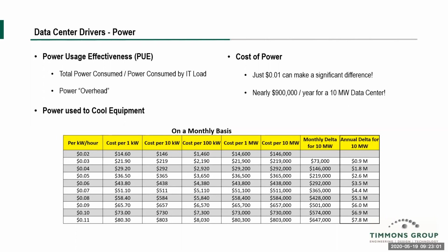We would be remiss if we did not touch on the cost of power as well. As you can see in the table below, just 1 cent can make a significant difference in the overall cost model of a data center. As you go up 1 cent for a 10 megawatt data center on a monthly basis, that's a $73,000 difference. Extrapolated yearly, that's nearly $900,000 per year for a 10 megawatt data center.